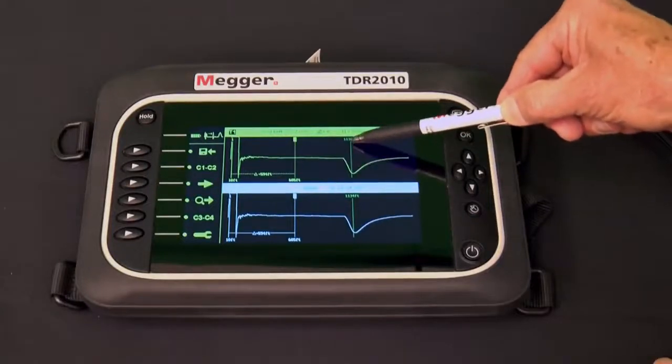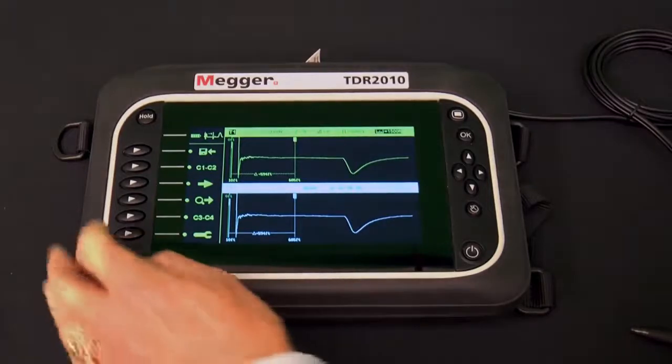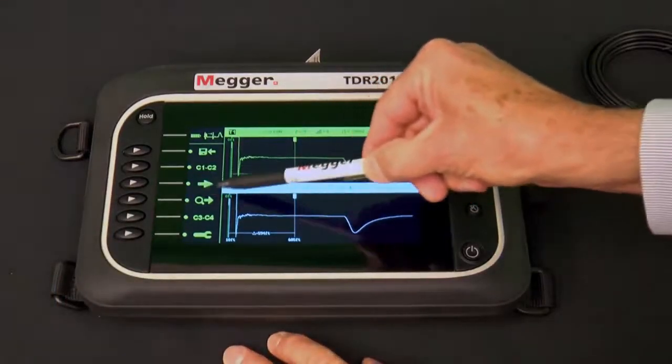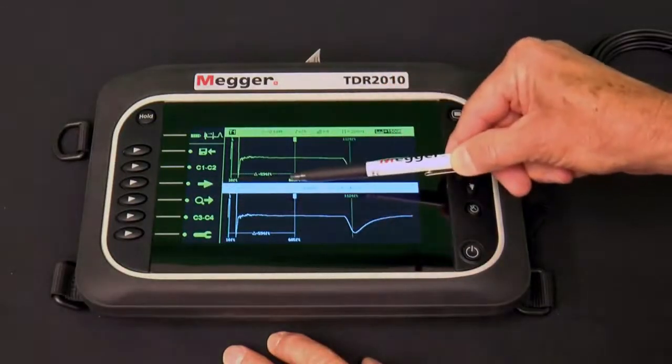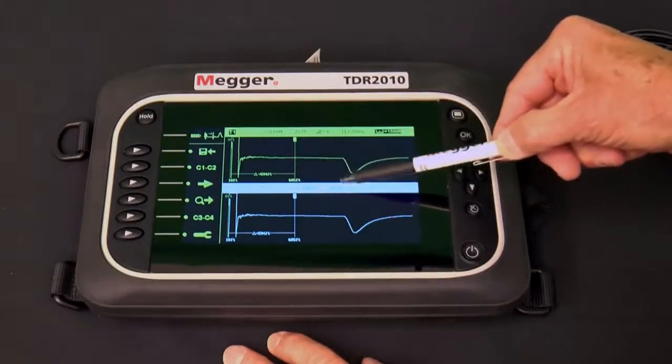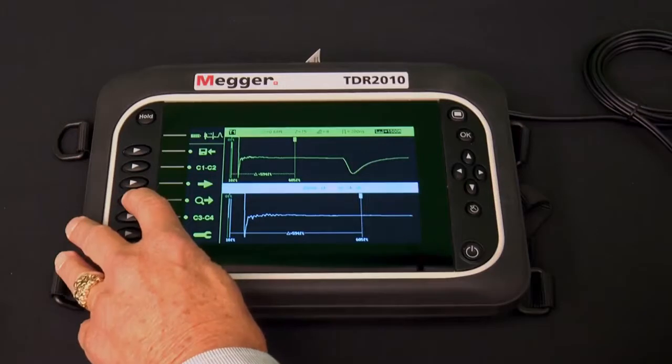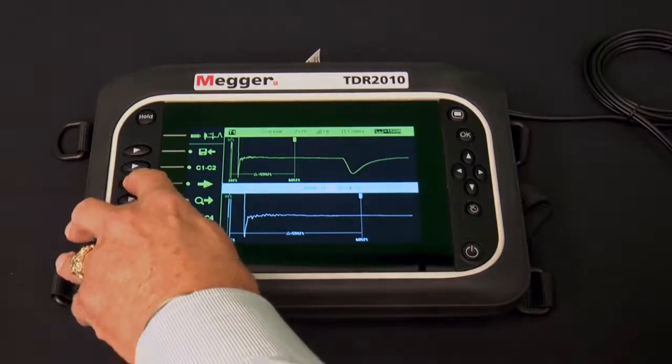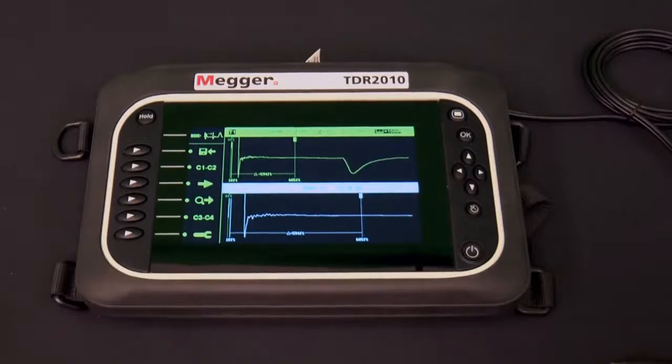The distance to that event is displayed at the top of that new cursor. The expert icon now changes to a large solid right pointing arrow. Note that the inactive trace has been replaced with a zoom trace of the active trace. Additional presses of the expert soft key will cause this new cursor to move to additional events that are further along the cable under test. Press the back key to exit the expert function.